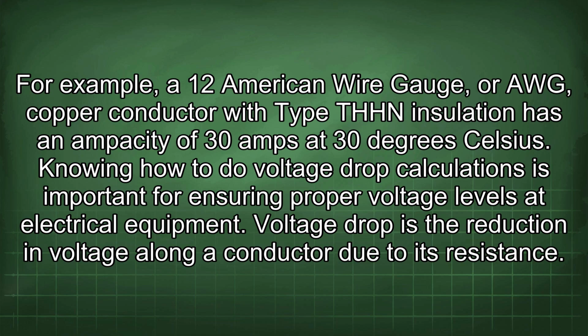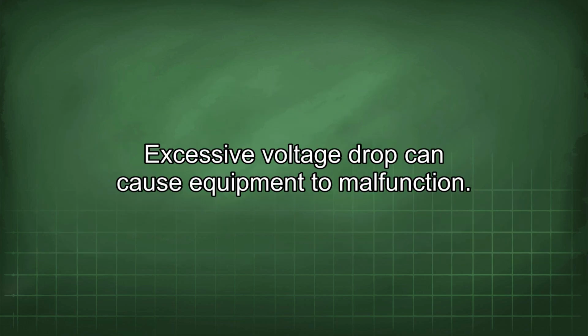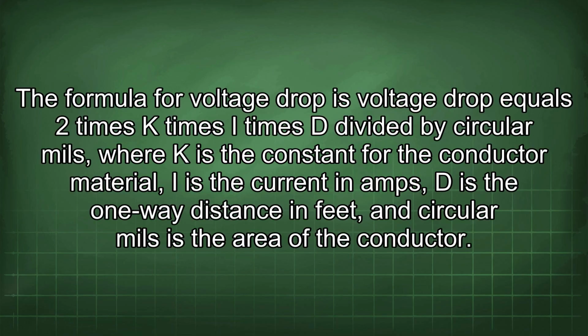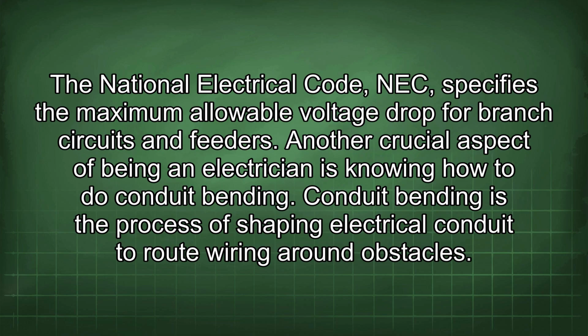Knowing how to do voltage drop calculations is important for ensuring proper voltage levels at electrical equipment. Voltage drop is the reduction in voltage along a conductor due to its resistance. Excessive voltage drop can cause equipment to malfunction. The formula for voltage drop is voltage drop equals 2 times K times I times D divided by circular mils, where K is the constant for the conductor material, I is the current in amps, D is the one-way distance in feet, and circular mils is the area of the conductor. The National Electrical Code, NEC, specifies the maximum allowable voltage drop for branch circuits and feeders.